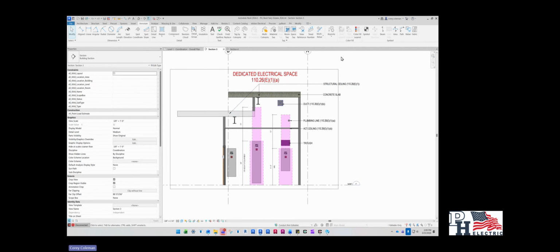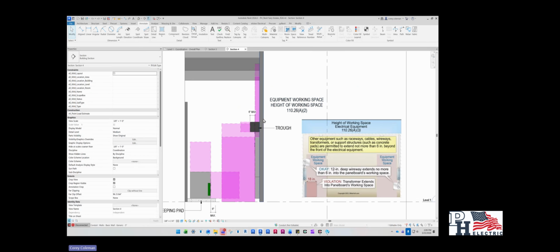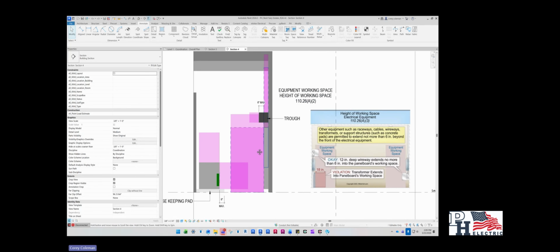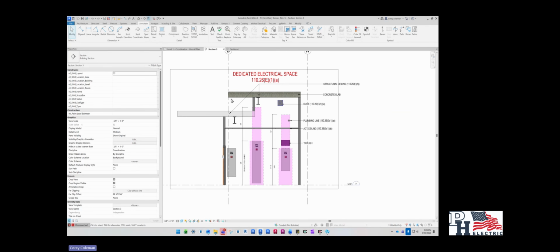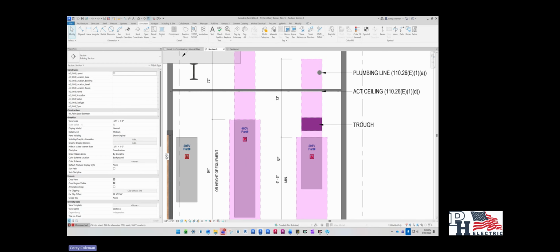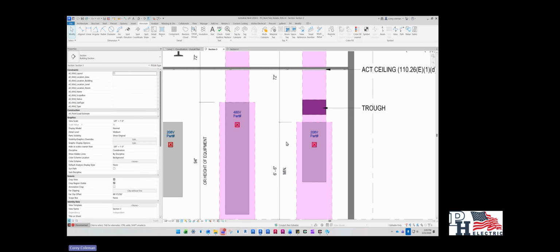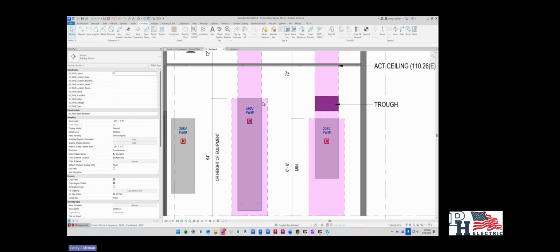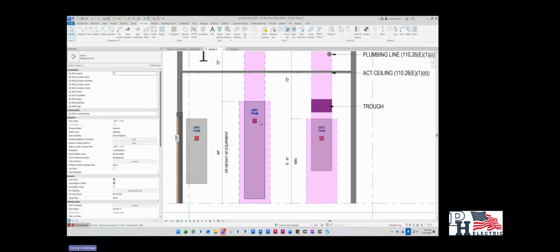Moving on to the height of the working space. The height of the working space, I'm actually going to jump back over here, needs to be at least 6'6" minimum, or the height of the equipment, whichever is larger. So for your 90-inch panels here, it's going to be much higher, and that should extend from the top of the equipment all the way down to the floor, or that 6'6" all the way down to the floor.